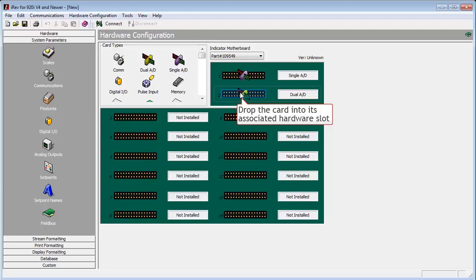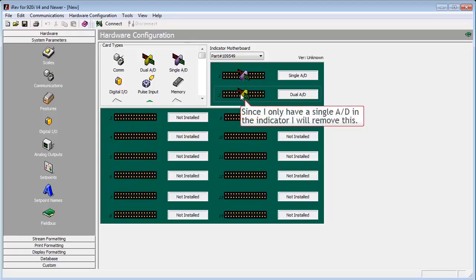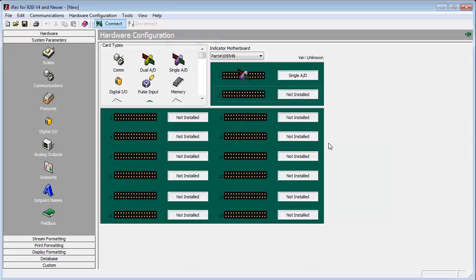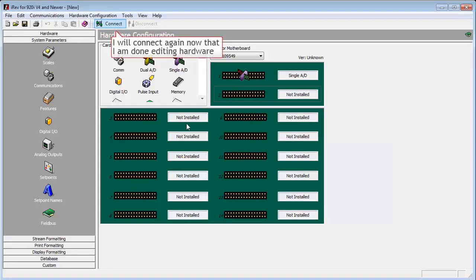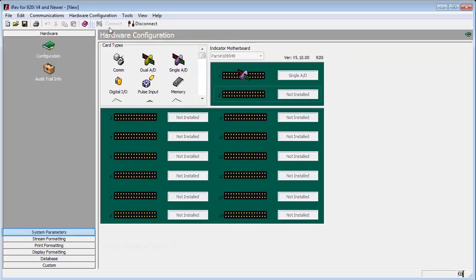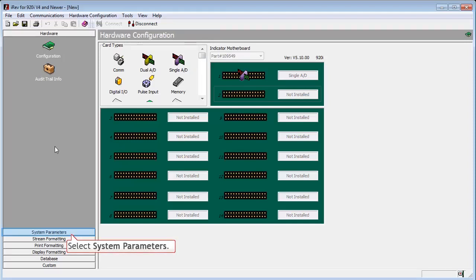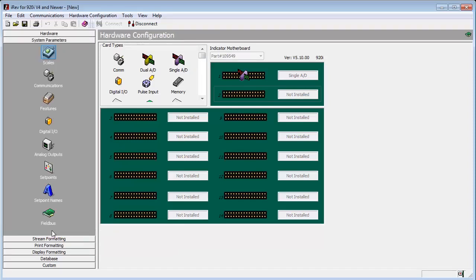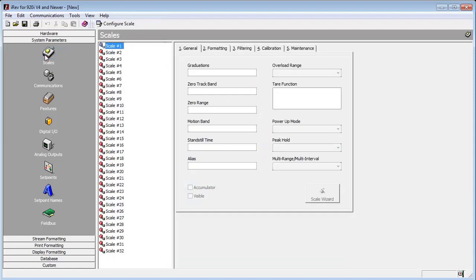For this demonstration, we will set up a 120,000 pound truck scale with a zero track band for zeroing off debris that may accumulate on the scale. To start, we will go to system parameters on the left side, click it, and then click on scales.